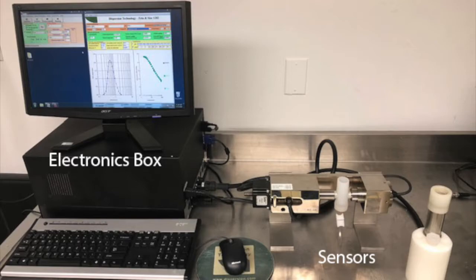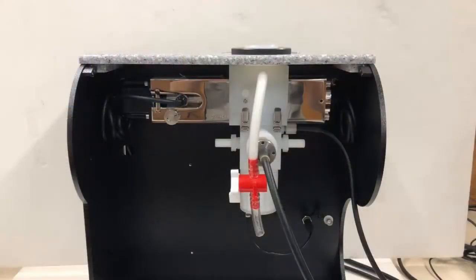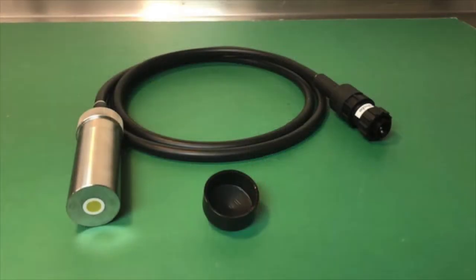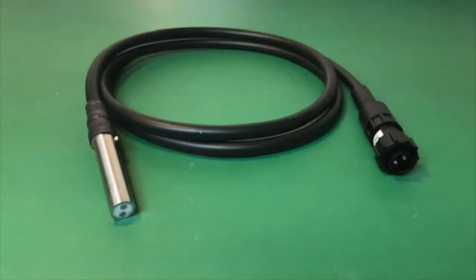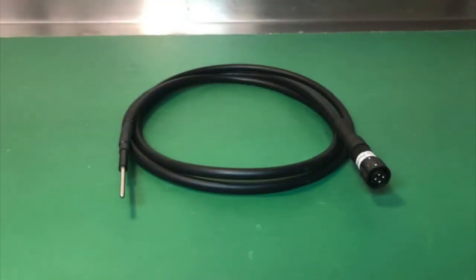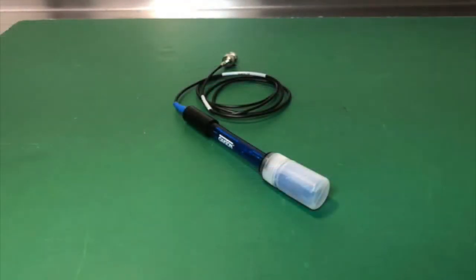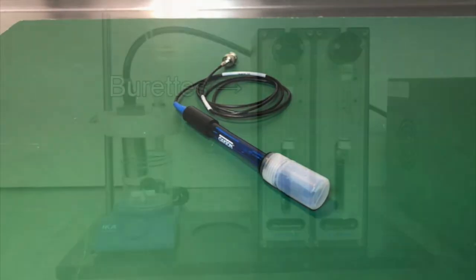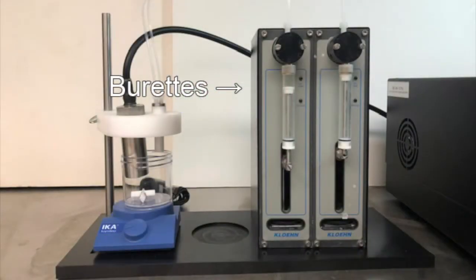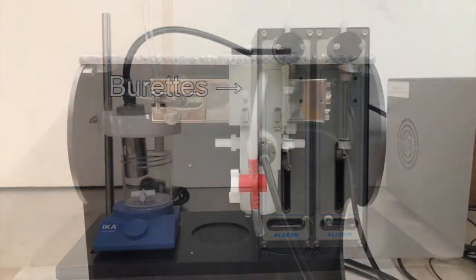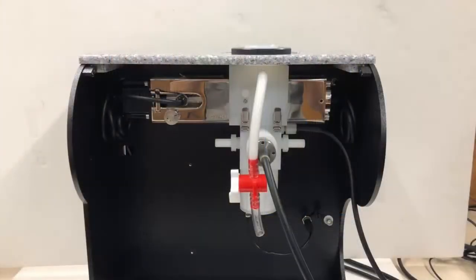These sensors include the acoustic sensor for particle size, the Zeta potential probe, the aqueous conductivity probe, which is optional, the temperature probe, which is also optional, the pH probe, which is optional as well, and burettes for titration, also optional. There are several types of stand for accommodating these probes, allowing for sample handling with or without mixing, as well as minimizing sample volume. This setup is the standard DT-1202 setup.